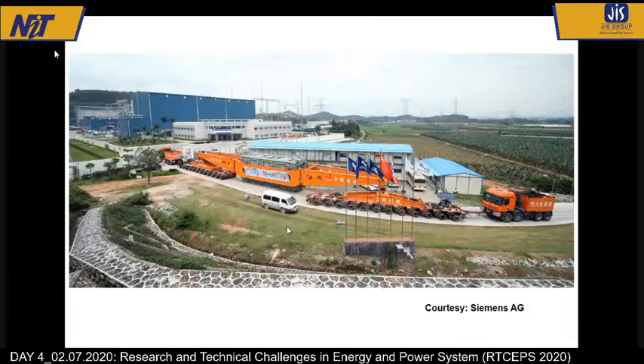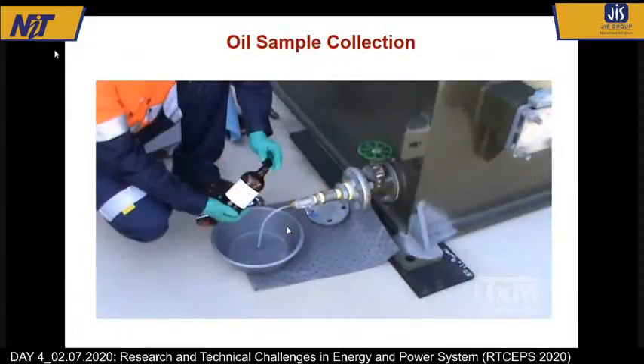Now, with this backdrop, this presentation is... But before that, when I am talking about the transformer, the first thing I have to mention is that in any transformer, there are 3 types of material used. One is the conductor, the second is the magnetic material, the third is the insulation. Conductors are generally copper or aluminium, that means metal. Magnetic materials are generally steel. Again, it is metal. So these two are very robust materials. This copper, aluminium, steel, they don't deteriorate all that easily.